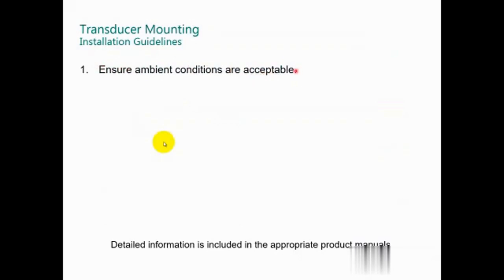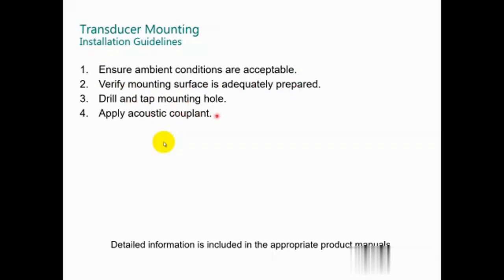Then ensure the ambient conditions are acceptable, depending on the temperature and humidity. For the sensor mounting, prepare and drill and tap the mounting, apply acoustic couplant, tighten the transducer to the specified torque. This is a key point.